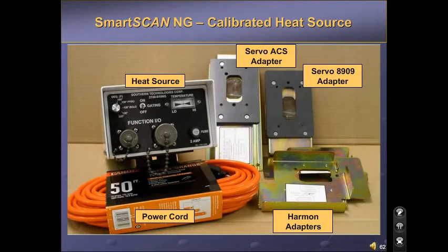The 2100 810 NG heat source is designed to calibrate hot box detectors in all types of weather conditions. It can operate from well below 0 to well over 110 degrees Fahrenheit. It is important to make certain the filter frames in the scanners have been cleaned before calibrating. Select the desired temperature. Plug it in and wait for about 10 minutes for it to come to temperature. The temperature has been reached when the needle in the window stabilizes in the center. Place the heat source on the scanner and you're ready to calibrate.